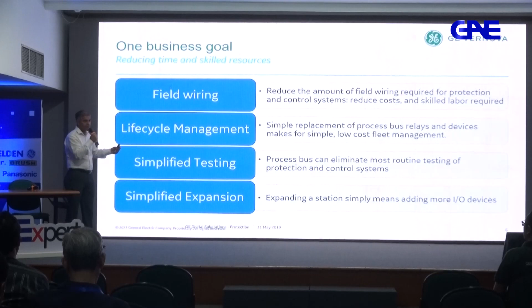Simplified expansion. If you want to expand your substation, it's quite easy. In a conventional substation, there is a lot of wiring involved. If you install a new bay, then you need to have new CT, VT signals, new cabling. You need to wire all those interfaces. For example, if you want to expand your busbar protection, you need to add new signals, you need to completely test. And if you completely test the busbar protection, probably you need to have a substation outage, right? So those things are very complicated. Digital substations simplify all those things, right?